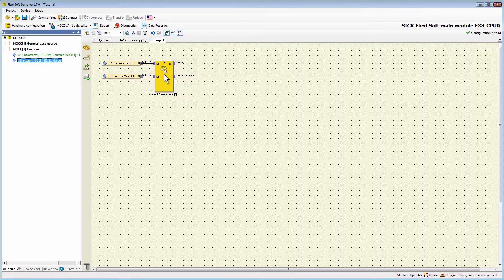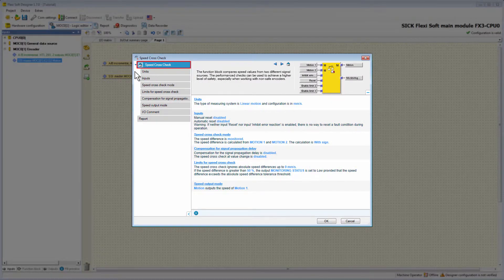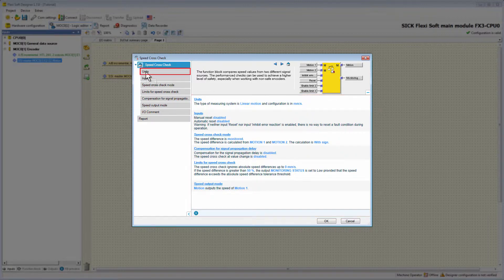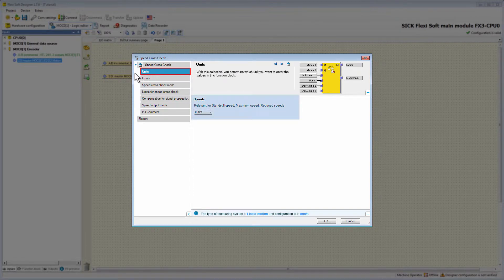To reach the configuration menu you need to double-click on the function block. The first tab which appears after opening shows a short overview of the current configuration — at the moment we see the default configuration of the SpeedCrossCheck. In the next tab Units, we have to define the unit which is used for calculating the speeds. Please note that the unit must match the motion type of the encoders; otherwise the SpeedCrossCheck turns orange and the configuration becomes invalid.